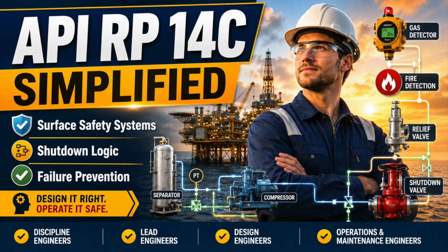The same discipline applies to low pressure. Low pressure may indicate a major leak. It may also threaten vessel collapse. Atmospheric vessels can rupture under small positive pressure and collapse under vacuum. Blocked vents, thermal contraction, rapid withdrawal, and failed blanketing systems can create dangerous conditions. Atmospheric does not mean no pressure hazard.